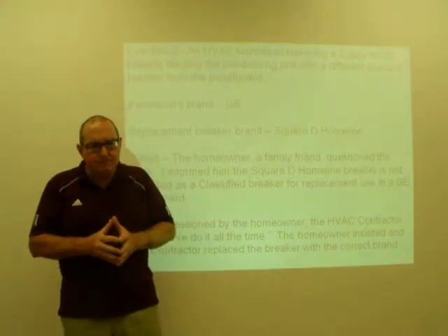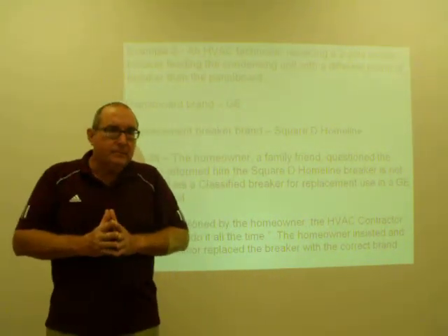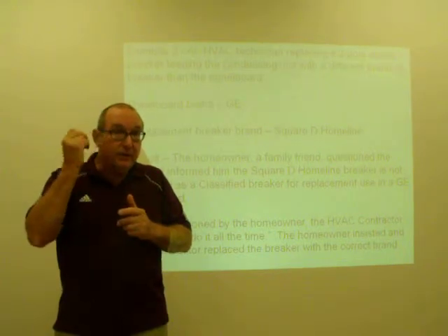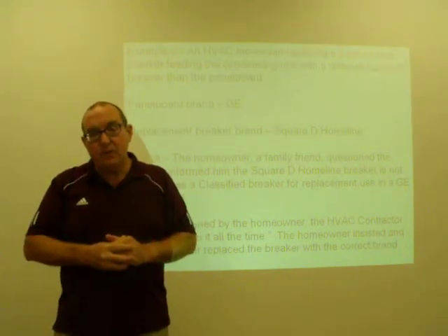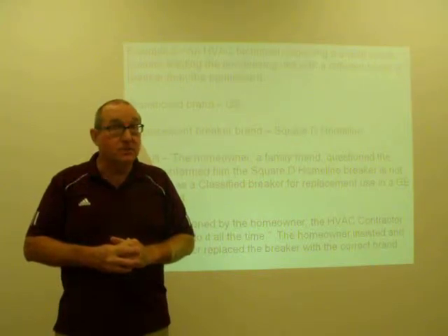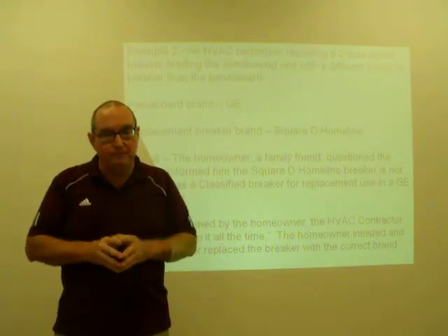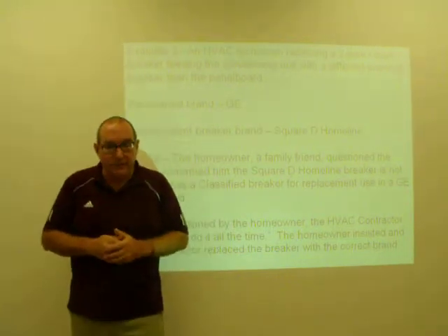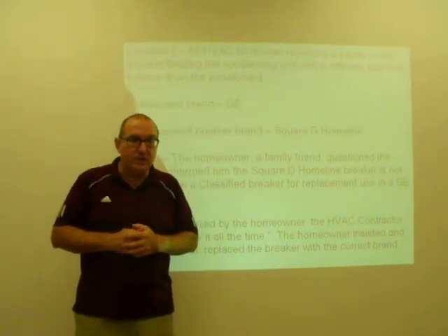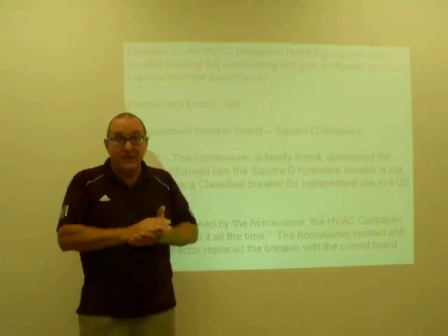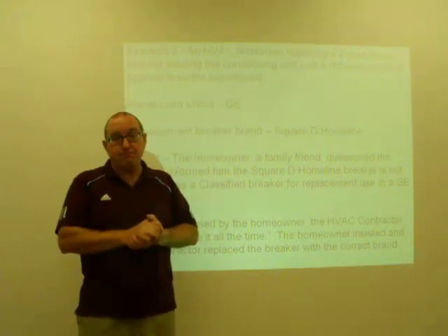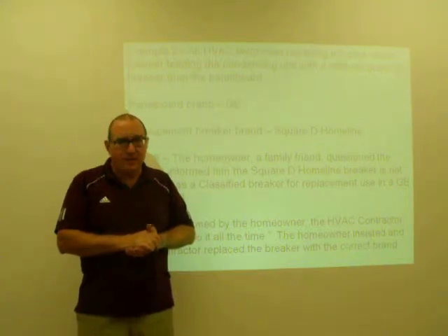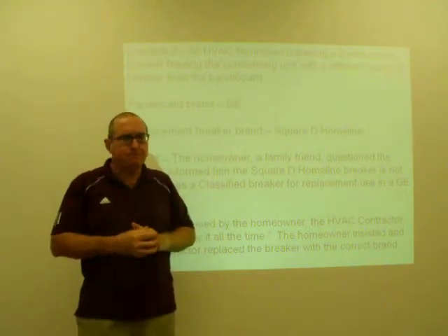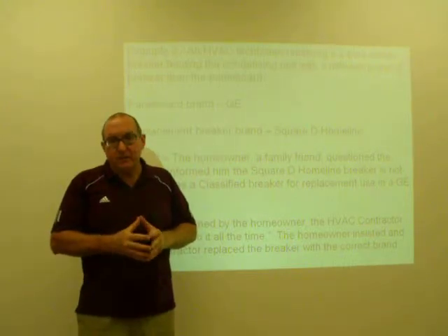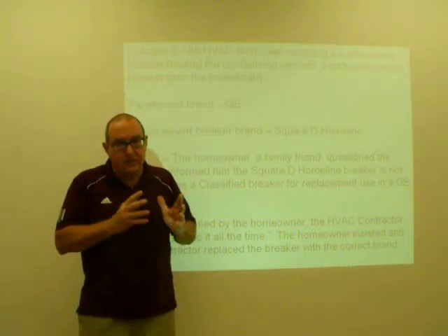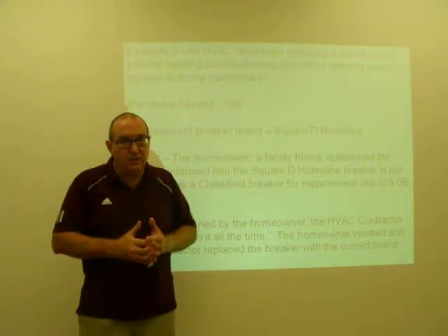The second example, at the residence, the air conditioning mechanic had to replace a breaker in the panel board in the house. He did so with the wrong brand of breaker, in the sense that it was not the same brand as the panel board. I believe that panel board was also General Electric. The breaker that the technician installed was a Square D Homeline breaker, which physically fit in the panel. But when the homeowner called me and asked me about this installation, because he was out of town at the time, he was a little concerned, wanted to make sure that the technician had done the right thing, because here in the state of Georgia, an air conditioning contractor is allowed to do their own electrical work.